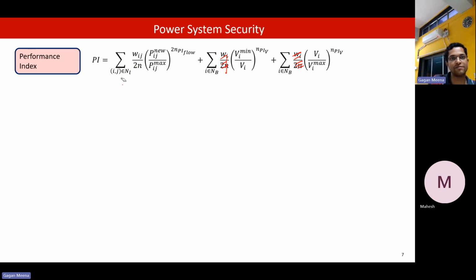If the flow on line L after the contingency is more than its maximum power transfer limit or power capability, if it is greater than the maximum limit, then this ratio, PL new divided by PL max, will be greater than 1. This performance index consists of 3 components. One corresponds to the line limit violation.